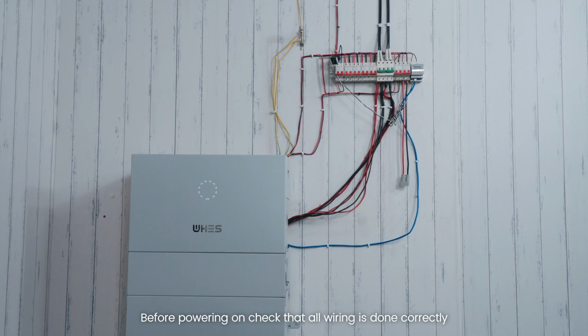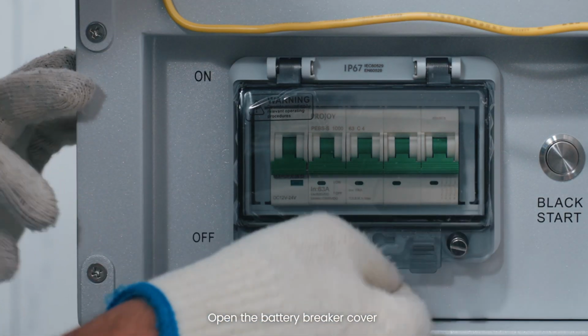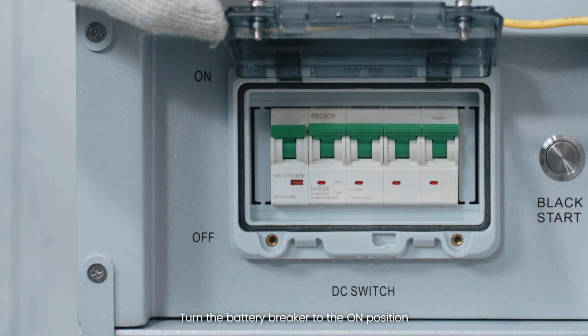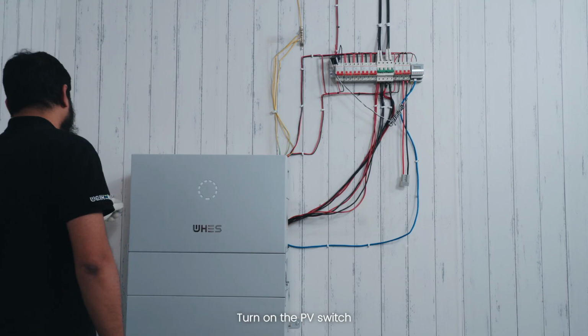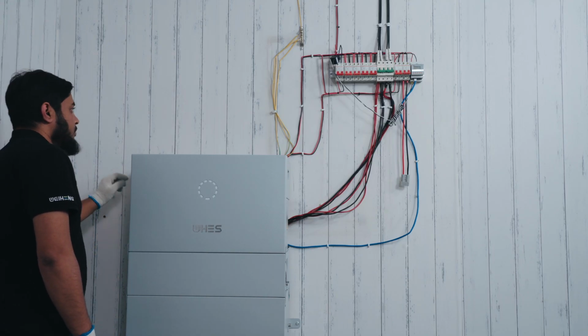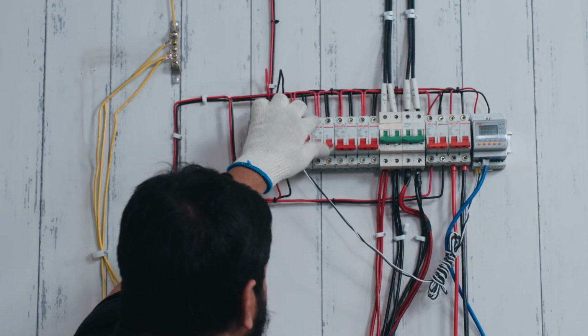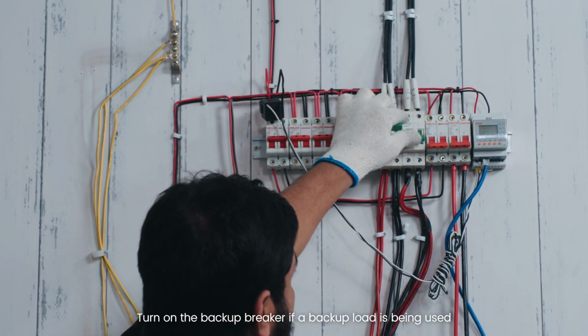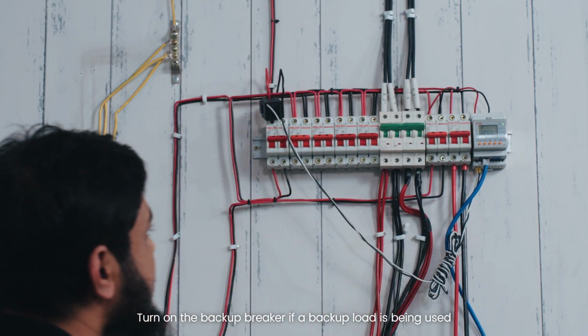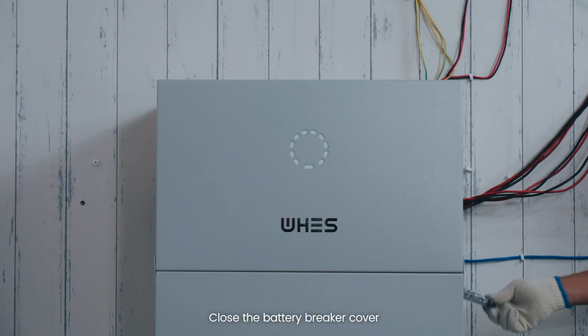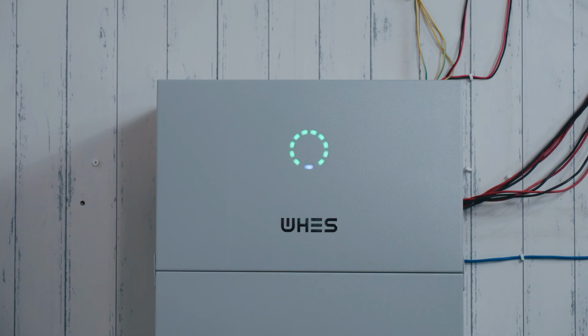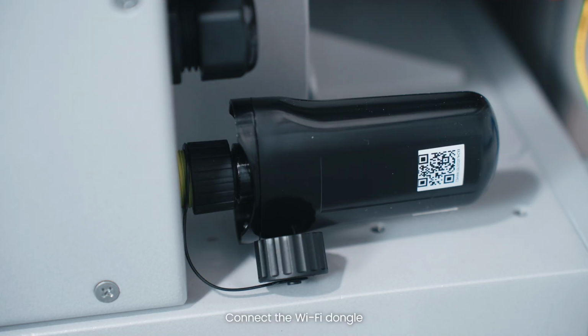Before powering on, check that all wiring is done correctly. Open the battery breaker cover. Turn the battery breaker to the on position. Turn on the PV switch. Turn on the grid breaker. Turn on the backup breaker if a backup load is being used. Close the battery breaker cover. Connect the Wi-Fi dongle.